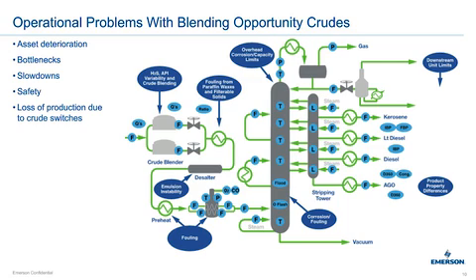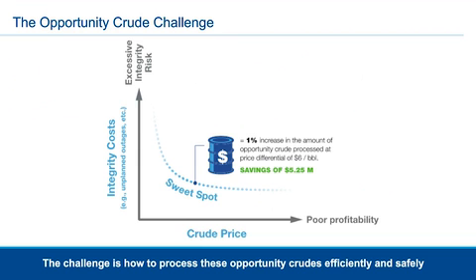And finally, there are problems utilizing traditional volumetric flow measurements for crude blending. The impact of changing properties of the crude on the flow accuracy is really significant, leading to inaccurate and suboptimal blends. If using mechanical meters such as PD or turbine meters, the associated maintenance costs to keep the meters accurate can also be large, as meter factors need to be adjusted anytime a significantly different crude component is utilized and needs to be metered.